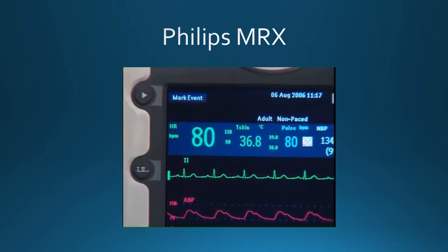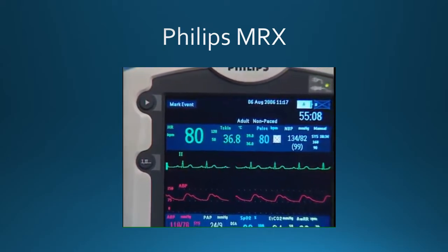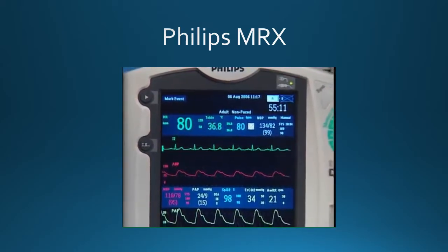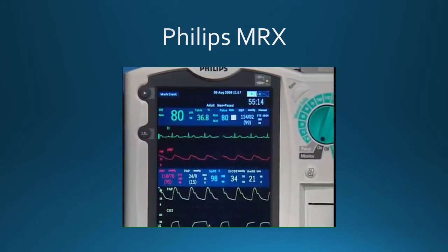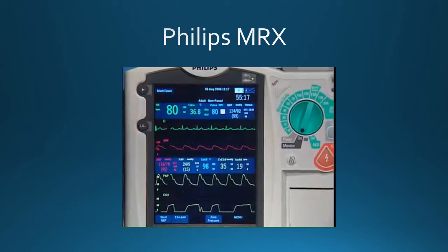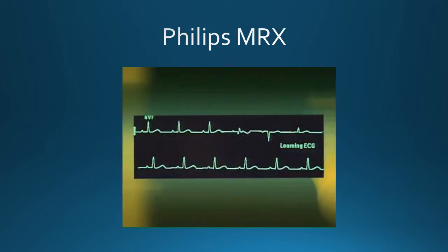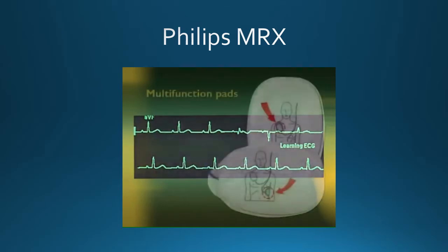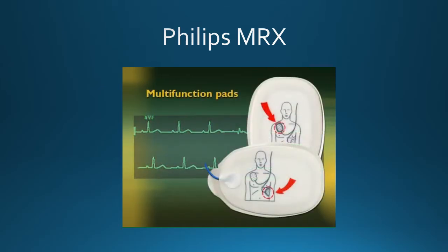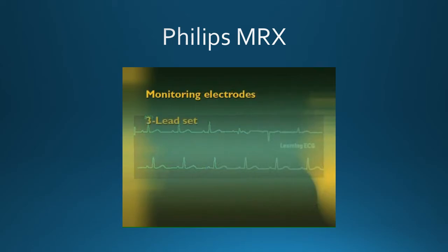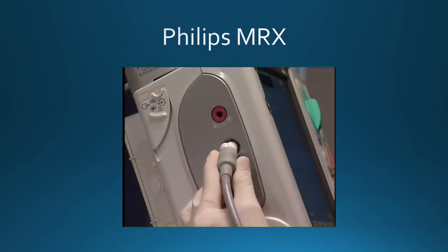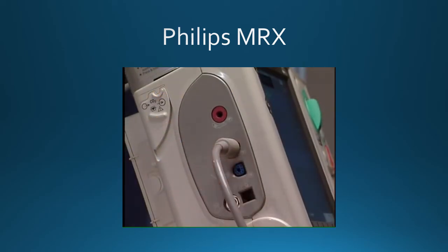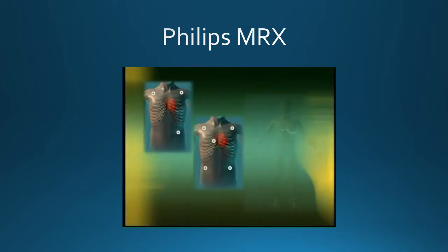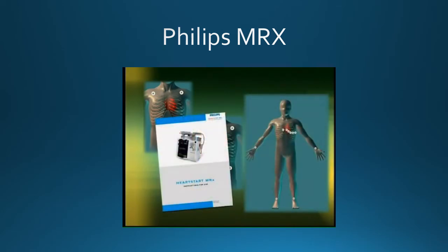With the HeartStart MRX, you can monitor ECG, pulse oximetry, non-invasive blood pressure, invasive pressures, end-tidal carbon dioxide, and temperature, and use the diagnostic 12-lead ECG function. When monitoring ECG using the MRX, you can use the multifunction defib electrode pads, or monitoring electrodes attached to a 3, 5, or 10-lead set. The ECG cable is color-coded and keyed to fit the ECG port on the measurement connector module. For proper lead placement in 3, 5, and 10 lead sets, consult the instructions for use.